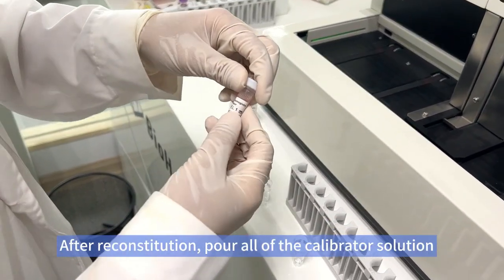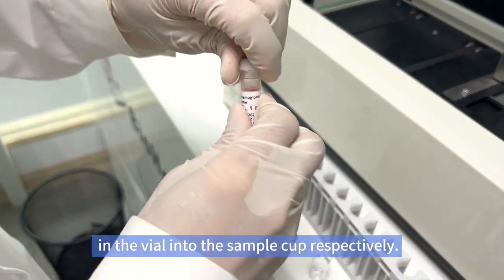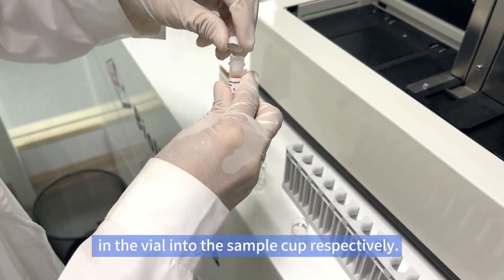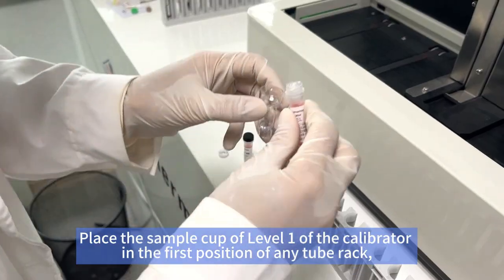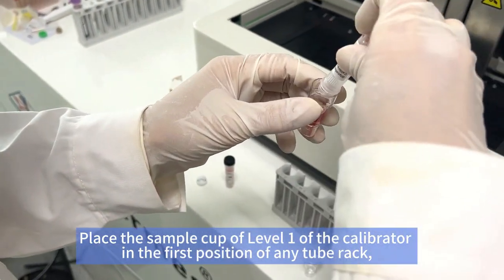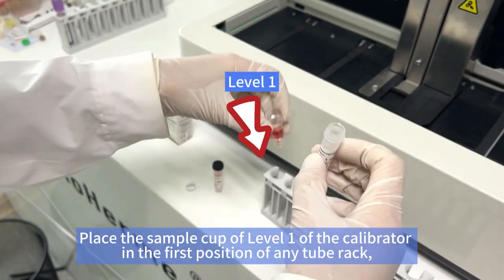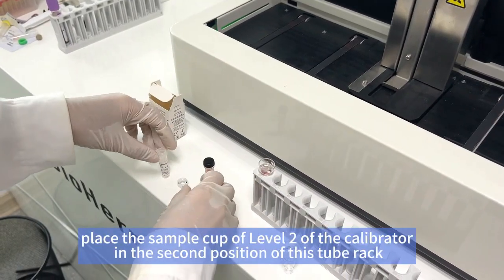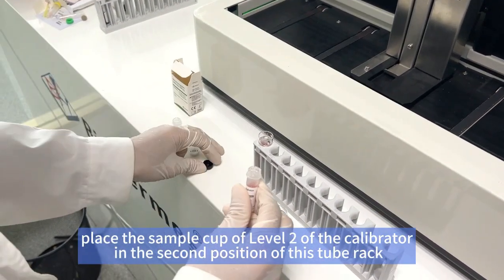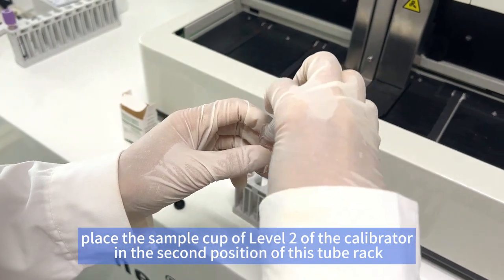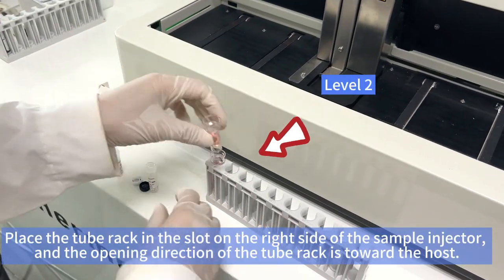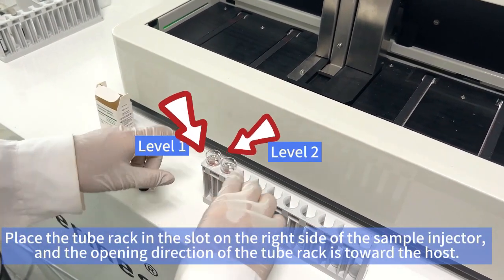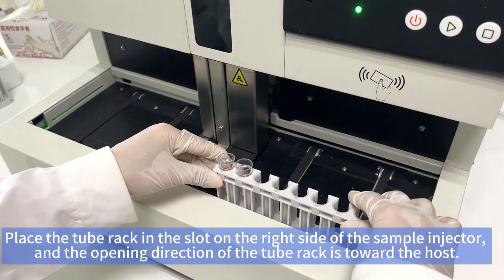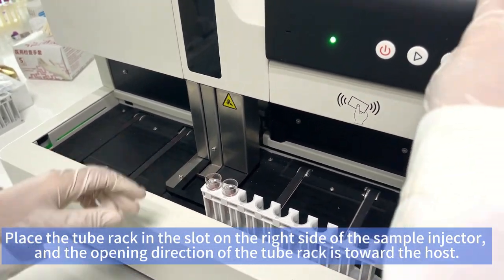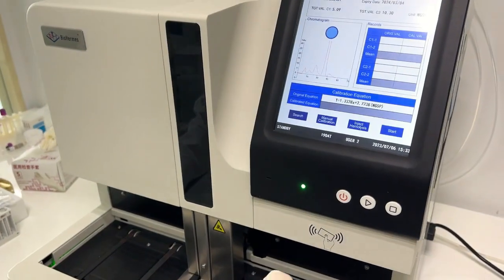After reconstitution, pour all of the calibrator solution in the vial into the sample cup respectively. Place the sample cup of level 1 of the calibrator in the first position of any tube rack, and place the sample cup of level 2 of the calibrator in the second position of this tube rack. Place the tube rack in the slot on the right side of the sample injector, and the opening direction of the tube rack is toward the host.